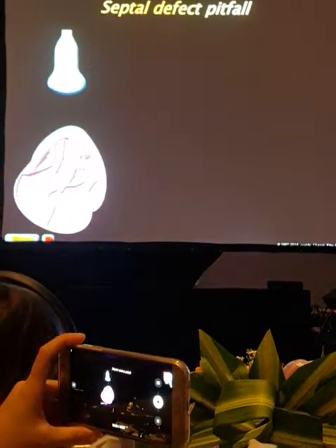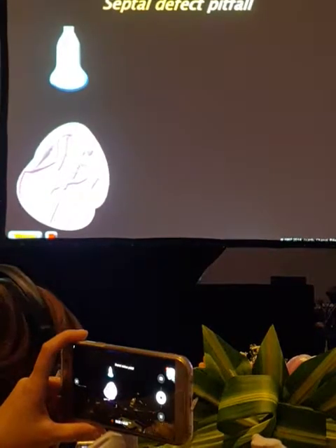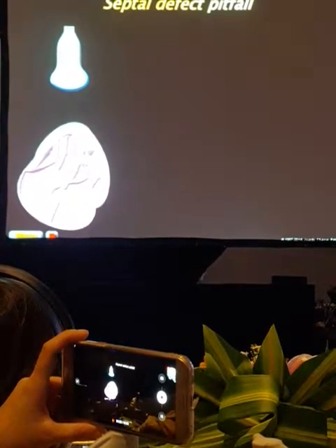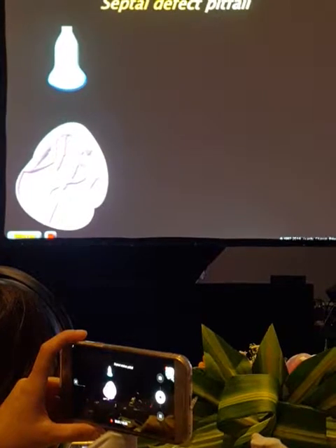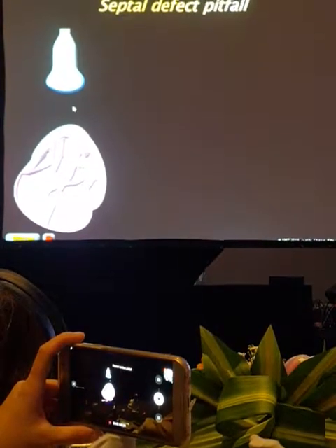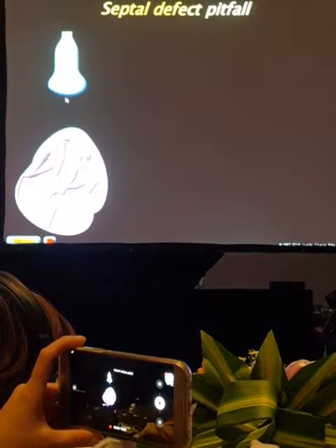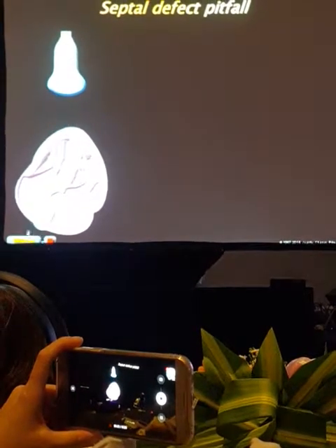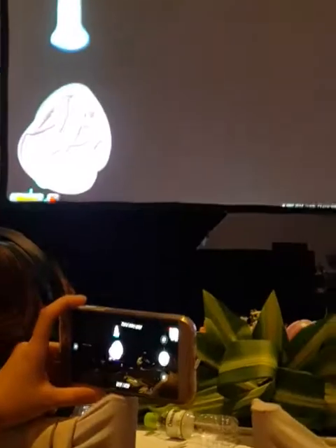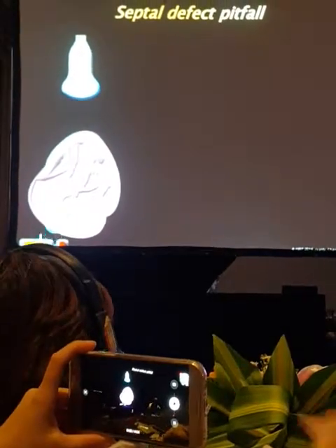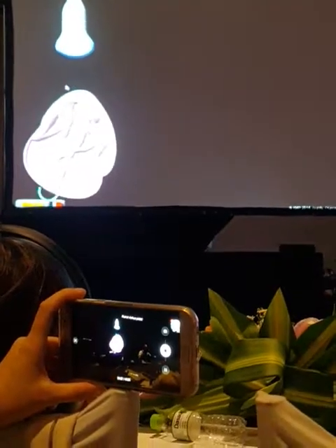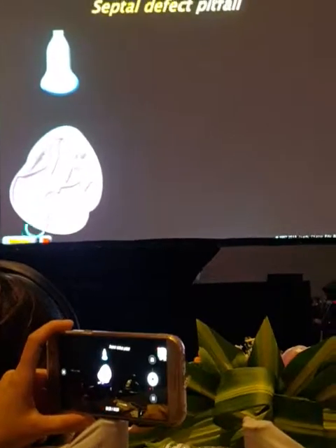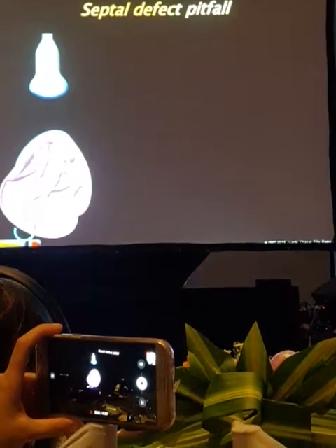If you look at ventricular septal defect, and you look in an apical view, which is what we often use when we do fetal echo, the interventricular wall is going to be almost parallel to the ultrasound beam. And if the beam is parallel, it has no interface to reflect on. So the machine will have no signal to provide. The machine will provide a dropout artifact. It will put a black hole that looks like a ventricular septal defect.